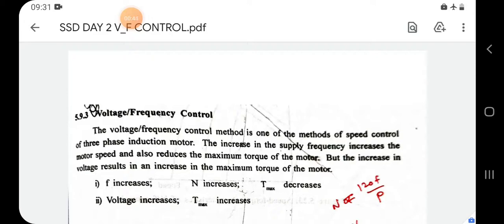The second method is the voltage-by-frequency (V/f) control, which is one of the powerful methods to control induction motor speed. We know the relation: N is directly proportional to 120f/P, or N = 120f/P. From this relation, if frequency increases, speed also increases but torque decreases.